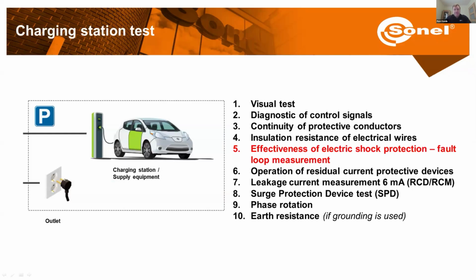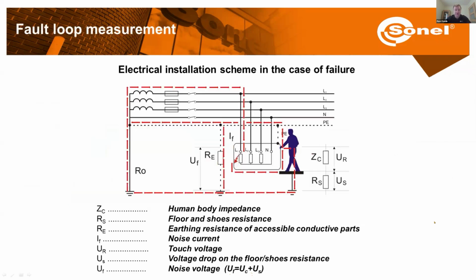Okay, then the next test, that's the effectiveness of electric shock protection. So that's the fault loop impedance measurement. We're going to do this on AC charging stations or the AC part of the DC charging stations. Now, why do we need to perform this measurement? If everything works fine, then the currents supplying our chargers flow from the phase conductor through the charger, and then return on the neutral conductor.